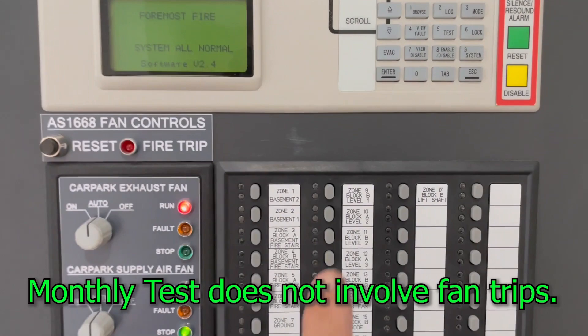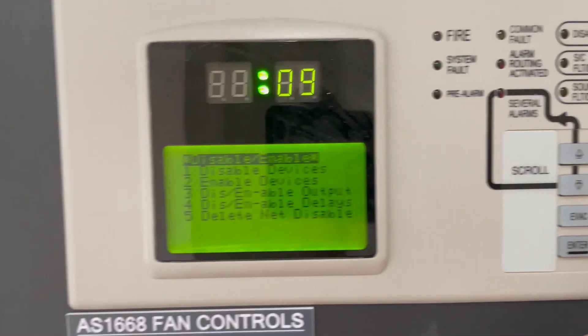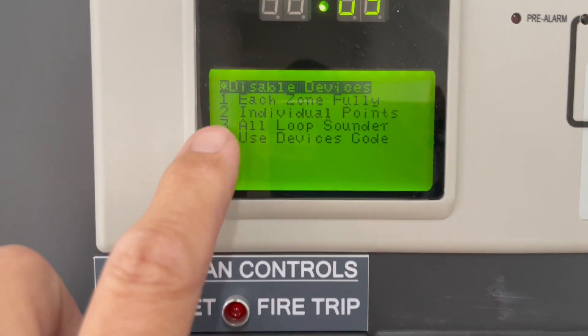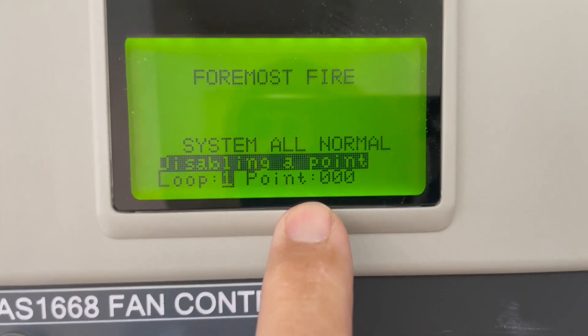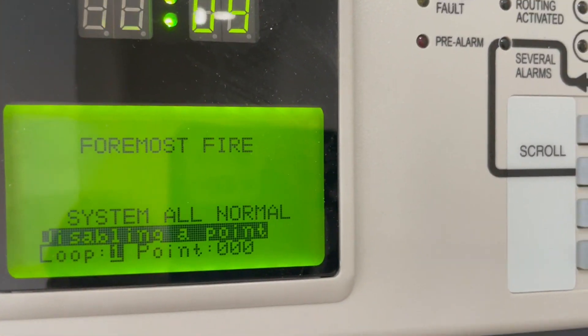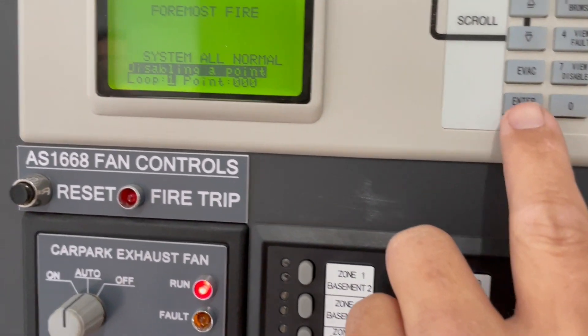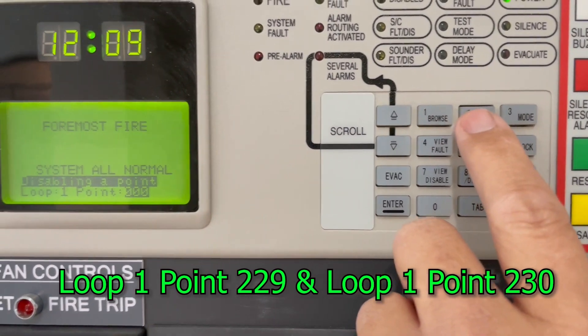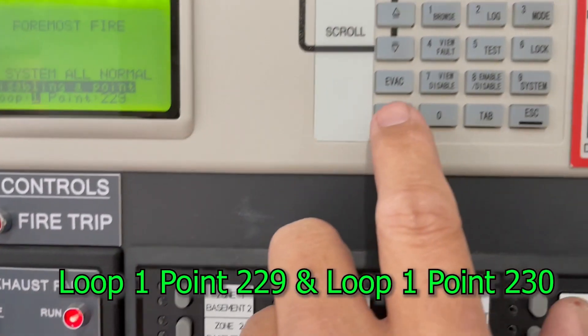This is how you do it. We go to Enable and Disable, then we're going to disable the device — number one. We're going to do individual points — number two. Okay, now it's loop one, and then what point we're after. This is loop one, already connected to the existing circuit — so 229. Press 229, then press one, it jumps to the next one, then enter 230, and press enter.